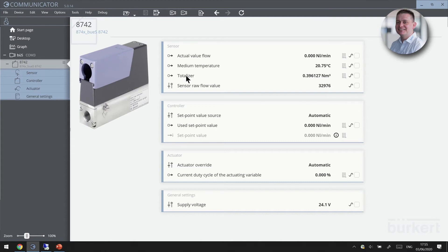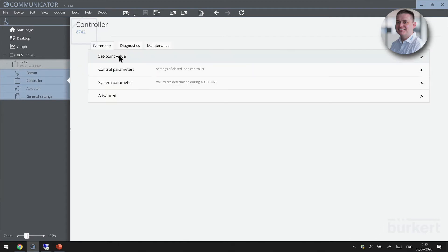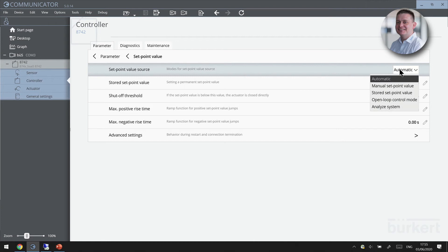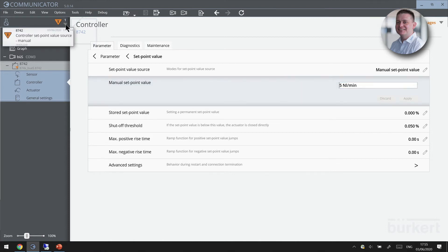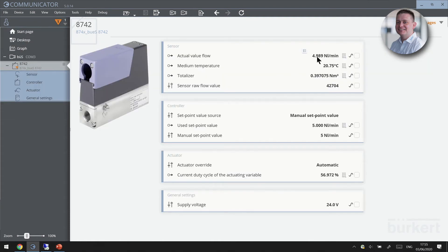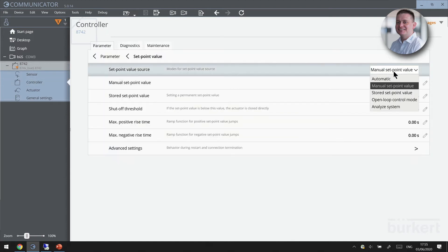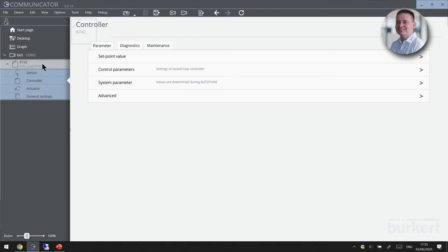At the moment our unit is looking for a signal from the PLC which is disconnected, so we need to commission the device and check its accuracy. We'll click onto controller and set the set point value from automatic to manual control. We can then set a set point of our choosing — 5 litres per minute. The unit is now in an orange MMR state, indicating the set point source is manual. We can see the actual flow value and totalizer counting up. Once we've verified these parameters, we go back to controller, click back to automatic, and the units return to zero.